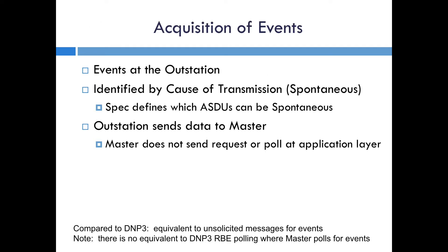Another function is called the acquisition of events. This is where the outstation can identify events or data changes and sends them to the master with the cause of transmission of spontaneous. The specification defines which ASDUs can be spontaneous, and in a similar way defines which ASDUs can be cyclic. The master does not send a request for this at the application layer — the outstation just sends it as the event occurs. This is very equivalent to unsolicited messages in DNP3, which also contain event data.